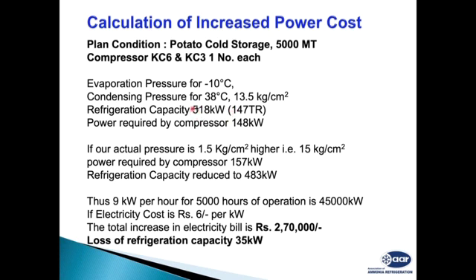Refrigeration capacity is around 518 kilowatt. The power required is 148 kilowatt. Now, if your pressure goes from 1.5 to 15, then the power required becomes 157 kilowatt. So see, this is positive. This is -10 evaporating, which means our evaporating pressure is higher than the atmosphere. In spite of that, there is air in the plant, and that costs us 9 kilowatt per hour.